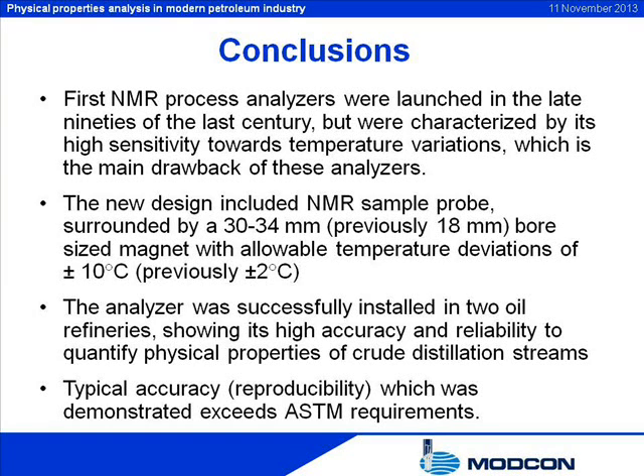The MOD 8000 Process NMR Analyzer was successfully installed in two refineries, showing high accuracy and reliability. It was used to quantify physical properties of crude distillation unit streams including density, API, IBP, FBP, T10%, T90%, RVP, flashpoint, pour point, cloud point, and freeze point. Typical accuracy and reproducibility demonstrated exceeds ASTM requirements.